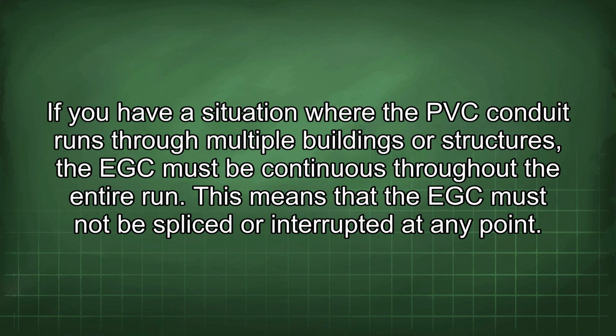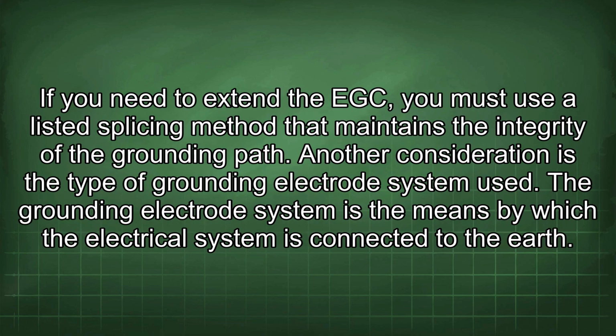If you have a situation where the PVC conduit runs through multiple buildings or structures, the EGC must be continuous throughout the entire run. This means that the EGC must not be spliced or interrupted at any point. If you need to extend the EGC, you must use a listed splicing method that maintains the integrity of the grounding path. Another consideration is the type of grounding electrode system used.